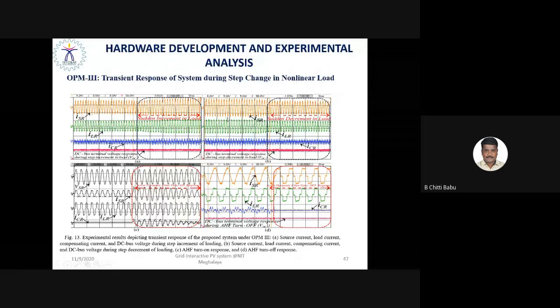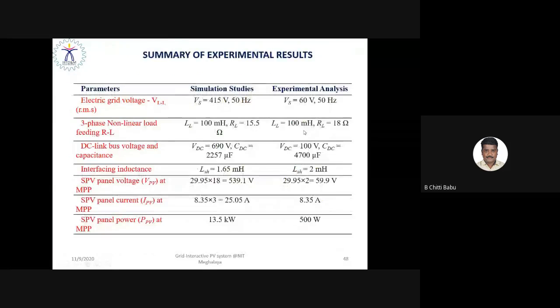So you can see throughout the case of sudden increment or sudden decrement in load, with the help of the outer voltage loop control with the precise tuning of the PI controller, it is able to maintain the DC link voltage constant, at par with the reference voltage of 690 volt. See, the current value changes during sudden increment or sudden decrement in load. So throughout the case, the load current profile is still stepped and it is a non-linear load, but still your supply current waveform becomes sinusoidal. Okay, that is what. So throughout the case, the DC link voltage is maintained constant, and moreover there is no circulation of neutral current. And this is the summary of the experimental result, with the simulation as well as the experiment.